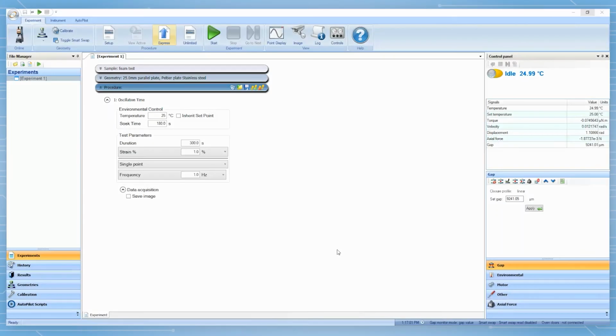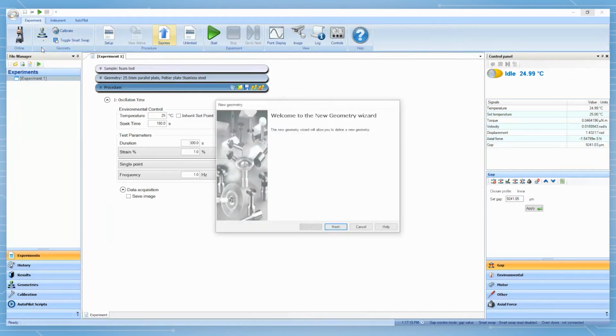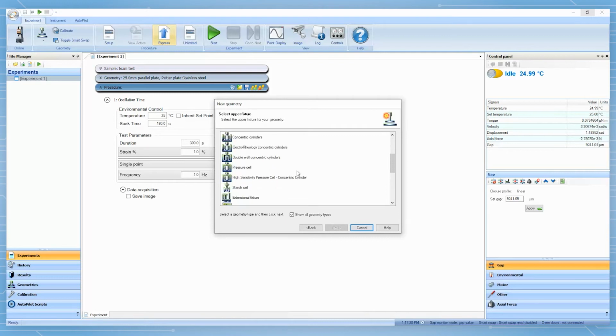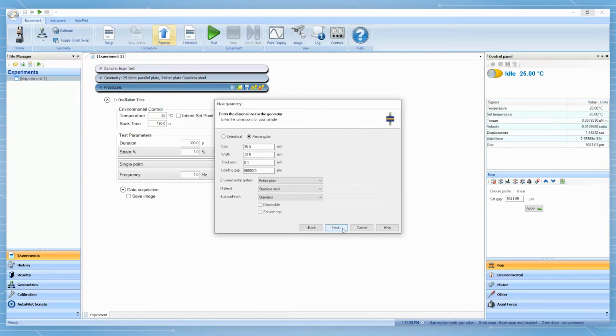If this compression geometry file has not been created previously, then the operator will need to create this geometry file before performing any compression testing. Under the geometry list, click on Add New Geometry. Then select Compression from the bottom of the list. Please note that this compression geometry will only be available if the instrument has the DMA mode key enabled.